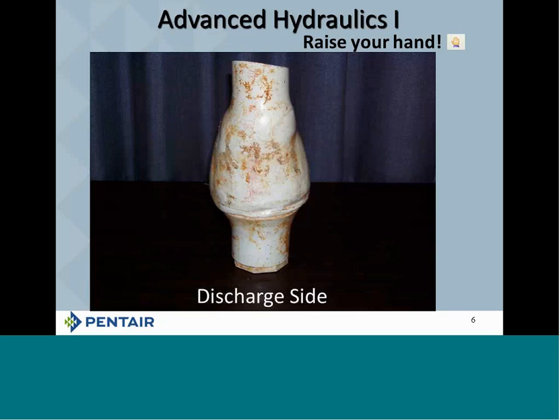But remember, just like that heat travels down that suction pipe, it's also going up the discharge pipe. However, on the discharge side, you can see what's happening here is that the pipe is swollen. You see that great big bloated area in the middle of that pipe.